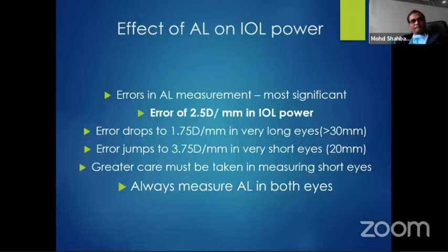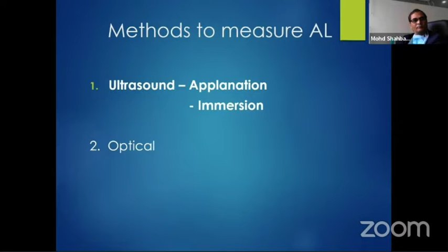Ultrasound applanation, ultrasound immersion, and the optical method are the methods of measurement of axial length. I will be concentrating on the ultrasound methods, that is applanation and immersion. In the ultrasound method, a transducer is used to send an ultrasound pulse, usually 8 to 10 megahertz, to create a sound beam which passes through the eye. The sound beam is reflected back at the interface of changing tissue density, like the anterior or posterior lens capsule. These echoes are displayed as vertical spikes rising from a baseline.